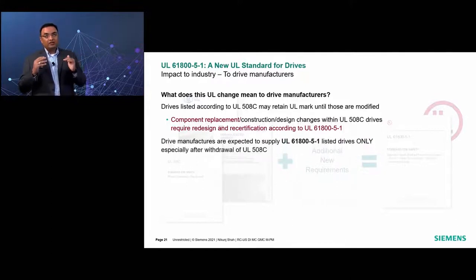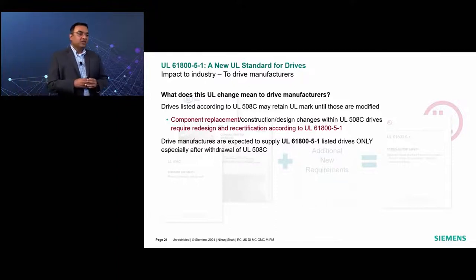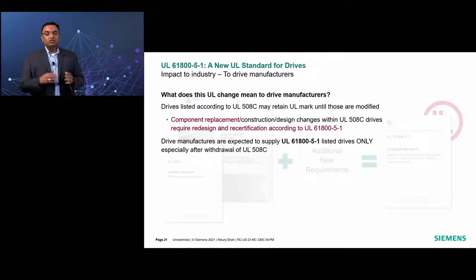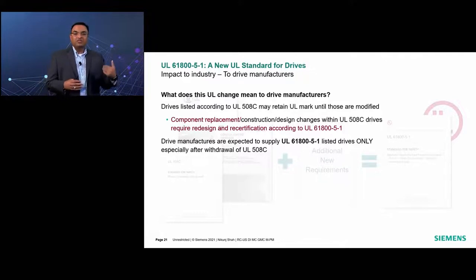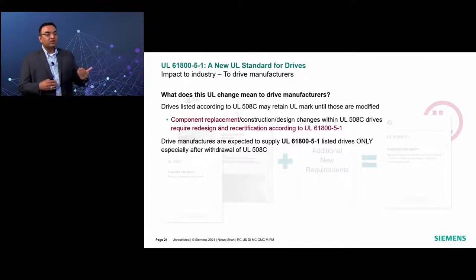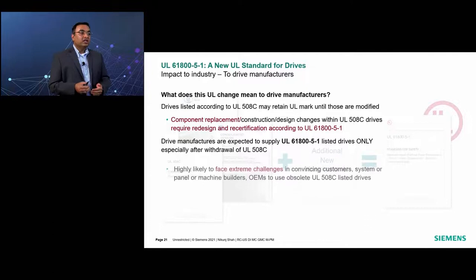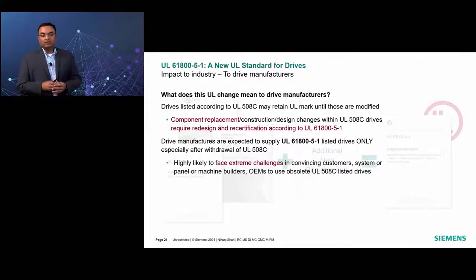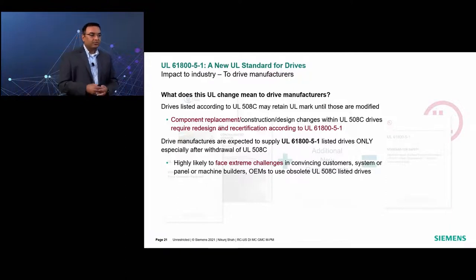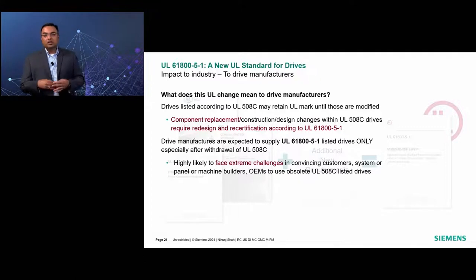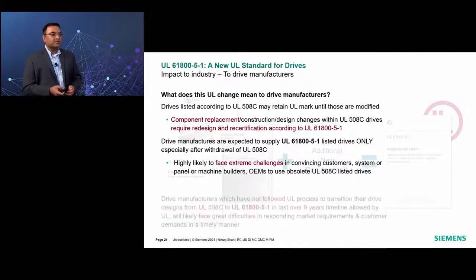Therefore, the drive manufacturers who have not made these changes are going to face more issues, especially because from last year, from February 2020, drive manufacturers are expected to supply only 61800-5-1 compliant drives in the equipment. And if they haven't done so, then they will be at a greater risk, or they will face more challenges in convincing the customers, system or panel builders or OEMs to continue to use their obsolete 508C listed drives.